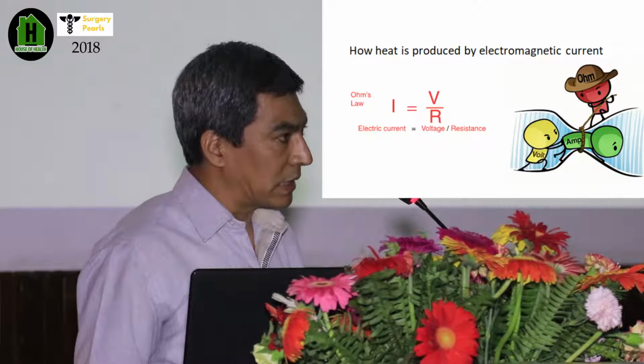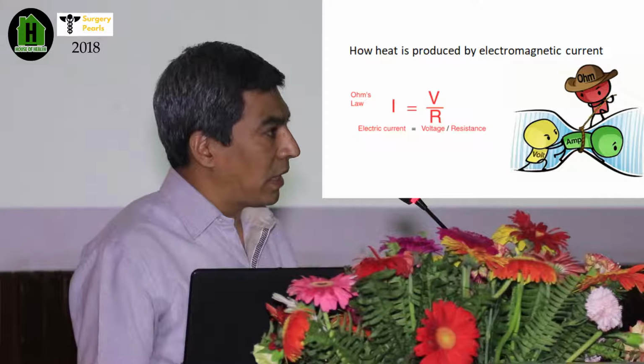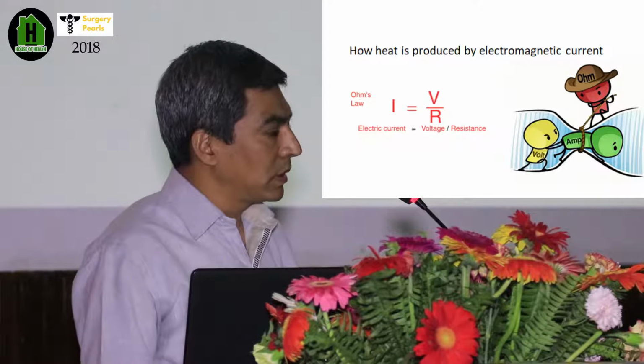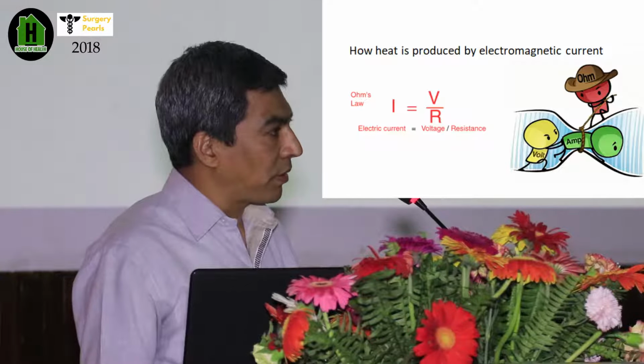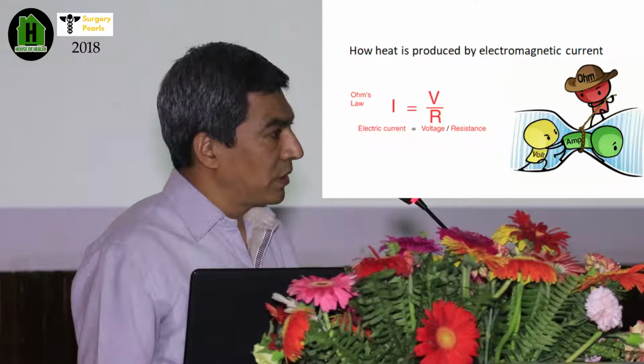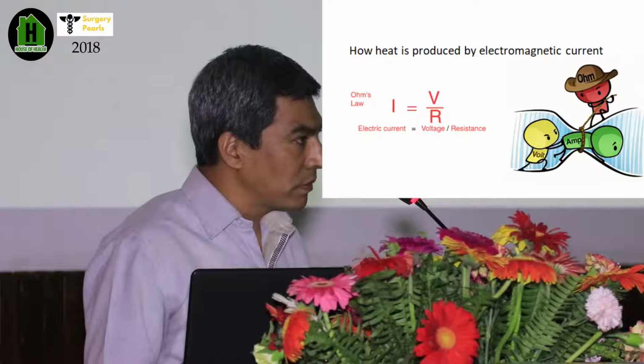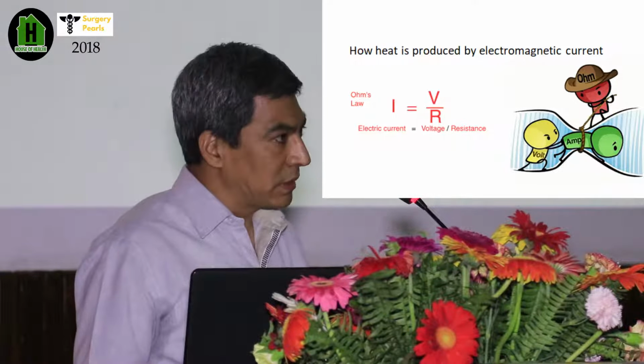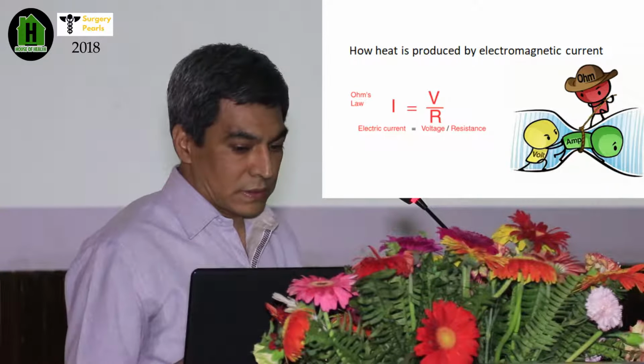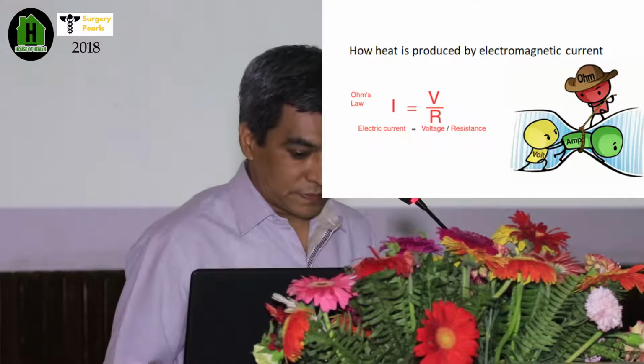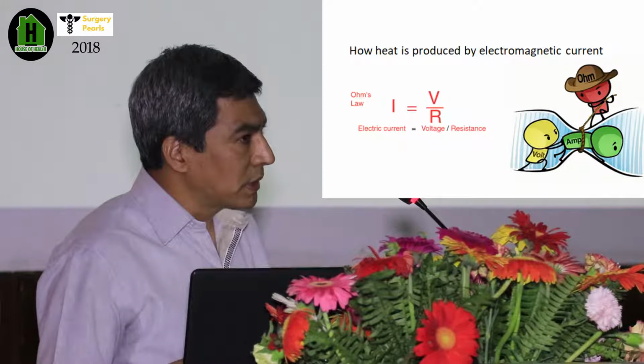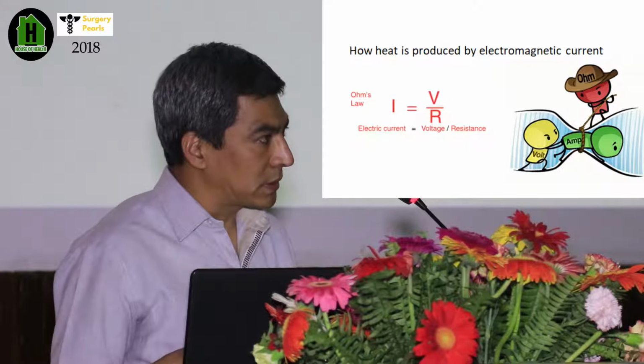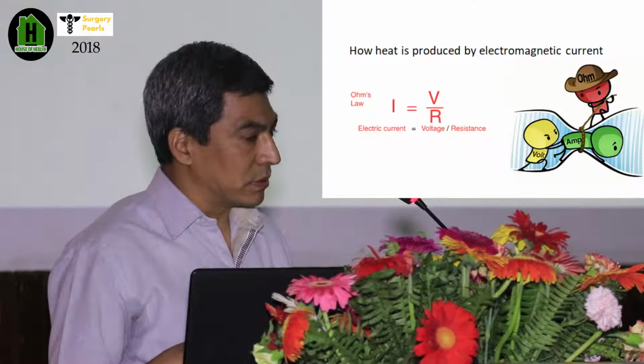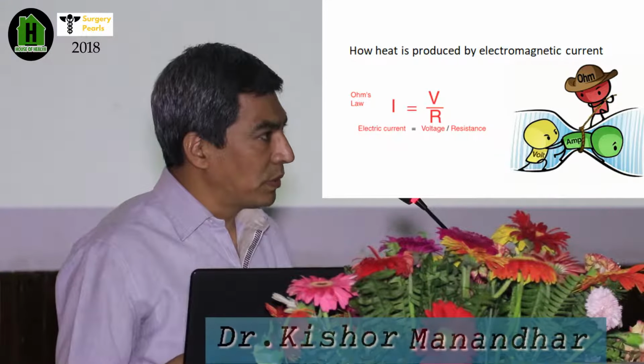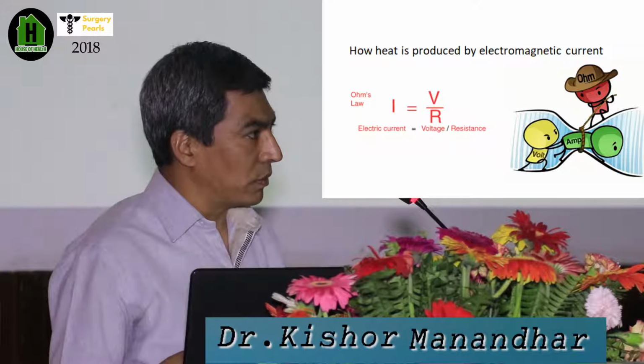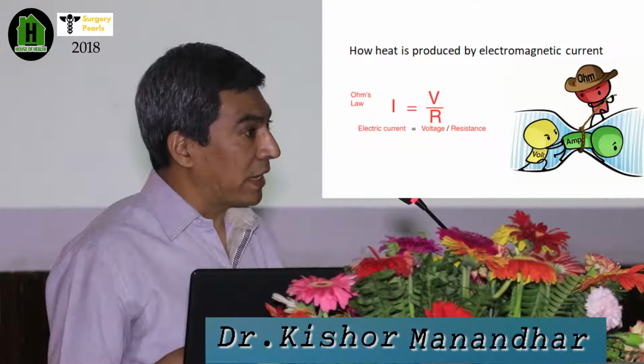Even though you do not remember the law itself, if the resistance is very high between the two different ends of the volts or the electric current, there will be heat production. If the resistance is low, the production of heat will be low. This is the basic principle of this electrosurgical generator. So here, while you're using coagulation or cauterization of the tissue, if you take a bulk of tissue, there is a low resistance. There will be no increase in temperature. The temperature rise will be very slow or low. So there you can't get the desired effect that you want.